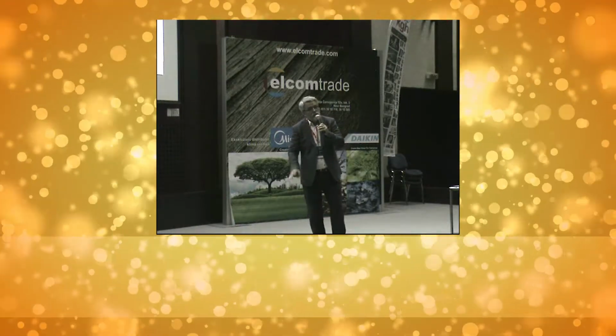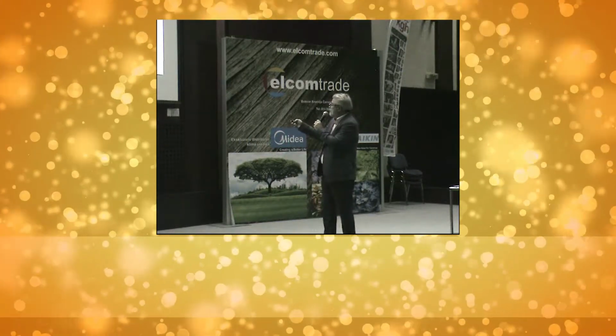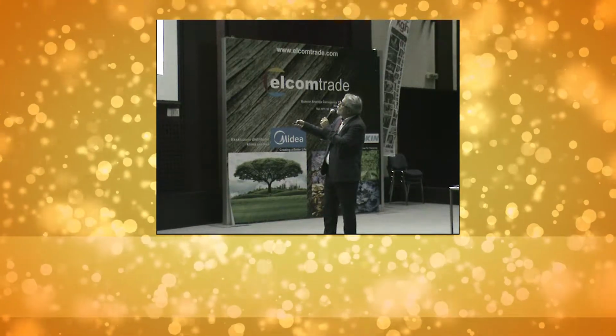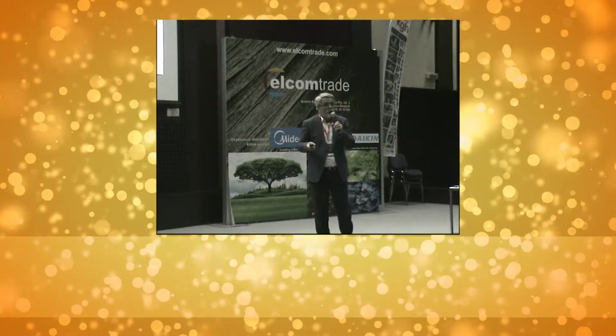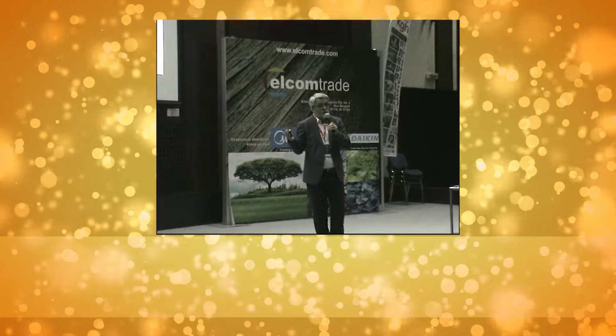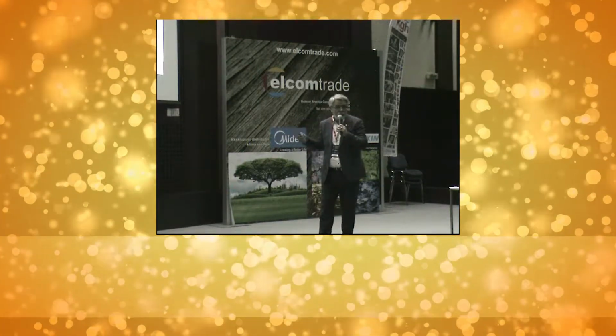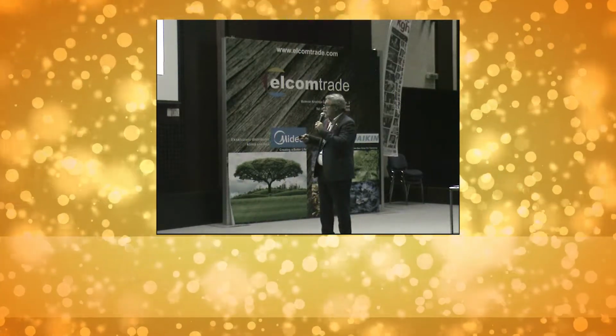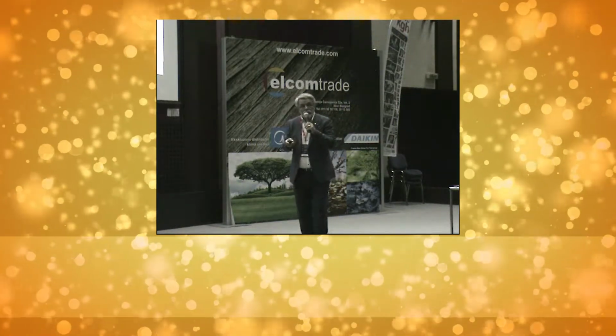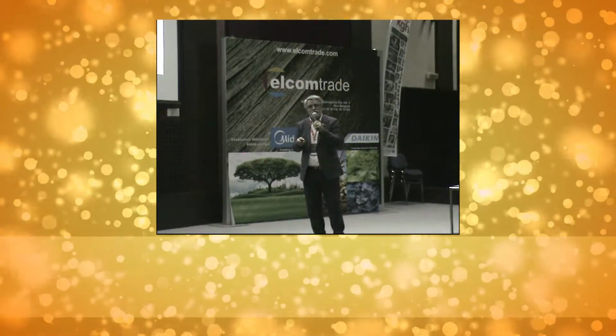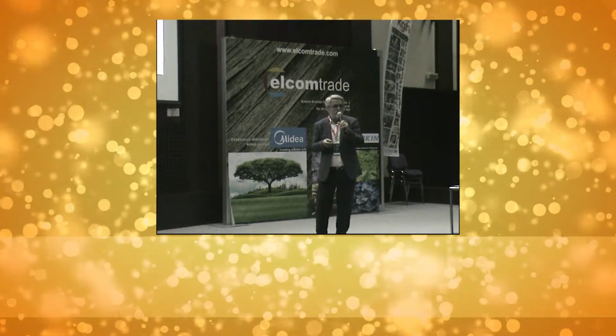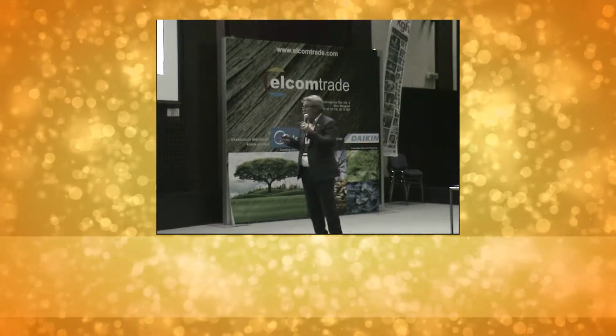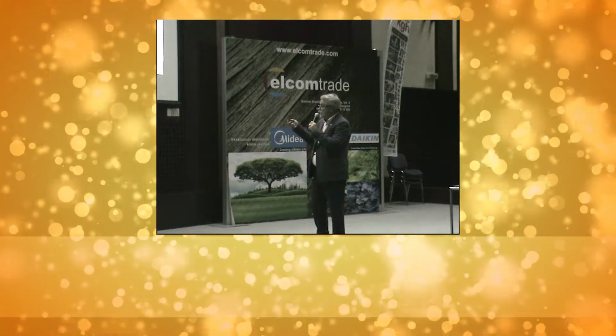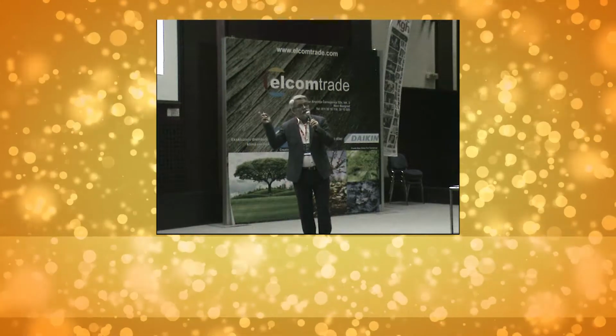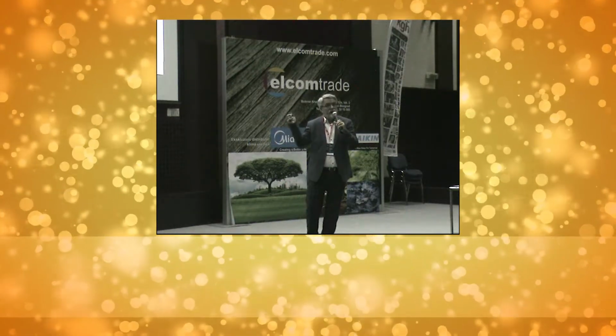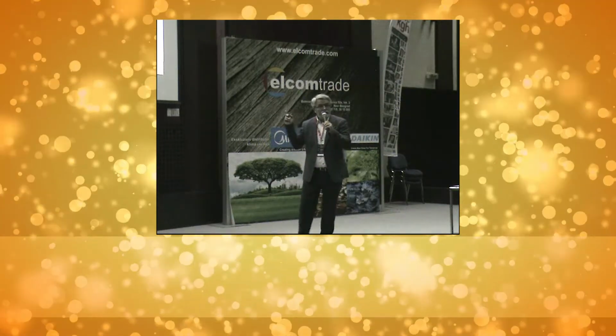When the temperature goes down under minus 10, we can stop the chiller, and the brine from the ice rink slab goes to the dry cooler. And so we can make a lot of economy, and it's a wonderful loop for recovering energy. After a couple of years that this ice rink has been running, there are around 60, 70 days per year in which the compressor is not running. And this is also very interesting, because using this kind of machine with a condenser cooled by a liquid could make a good recovery loop in a place like this.